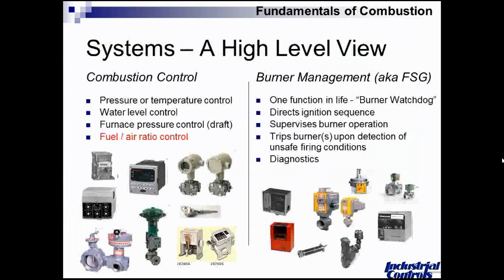FSG stands for flame safeguard — anything in that family of acronyms describes the brains inside that system. It can be the red box on the left-hand side, which is a Fireye full-function programmer, or on the right-hand side the Honeywell version. That acts as the brains — it's the core of the system. There are also PLC-based systems out there, but by and large these committed-function devices are used extensively for that purpose.